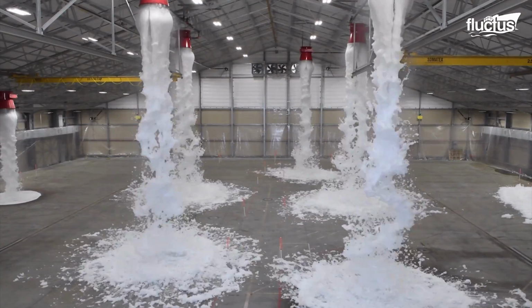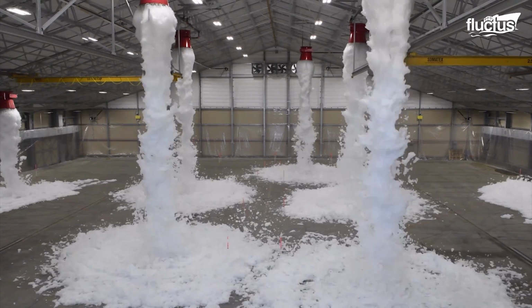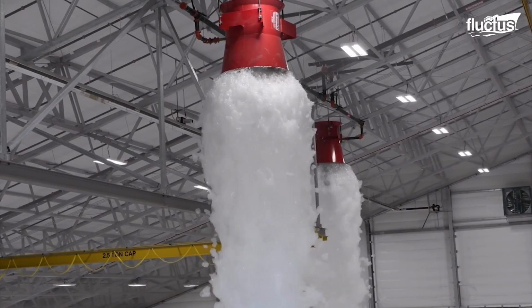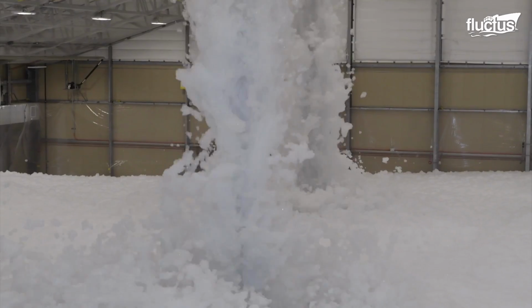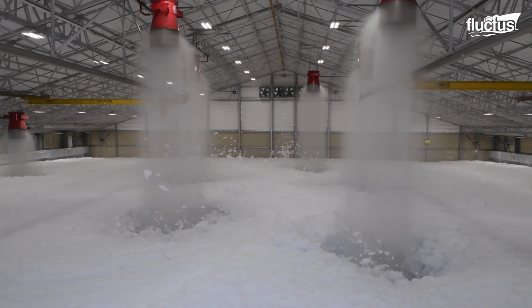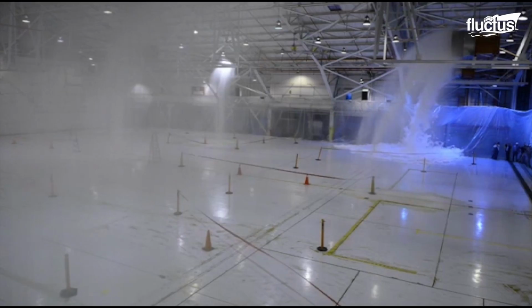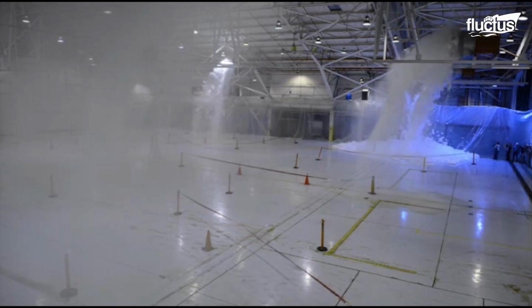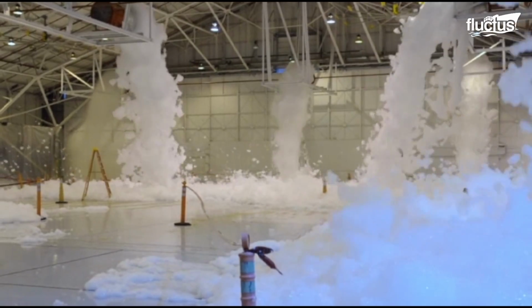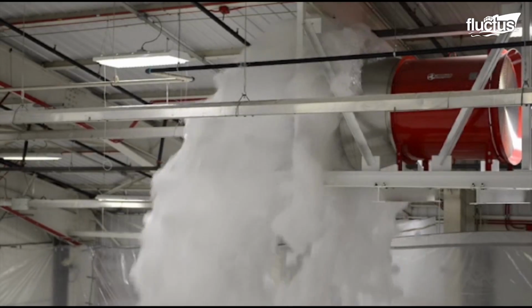The foam fire suppression systems installed in the U.S. military's certified hangar base are capable of covering 90% of the entire hangar floor with at least 3 feet of foam in 4 minutes. If a hangar bay is incapable of hitting these metrics in terms of speed and extinguishing efficiency, it may have to reinstall or replace systems entirely.